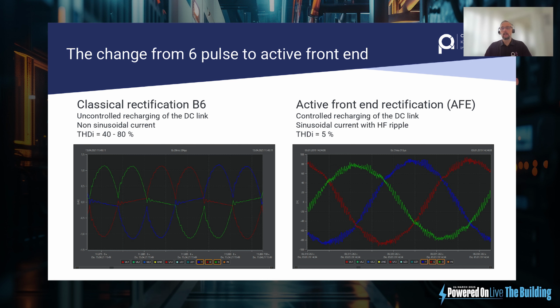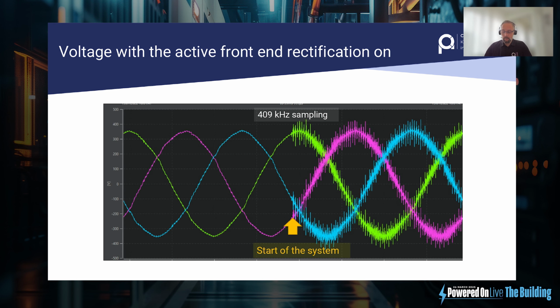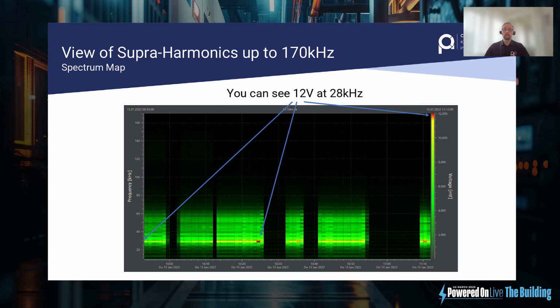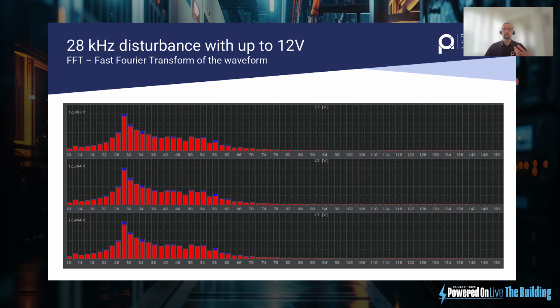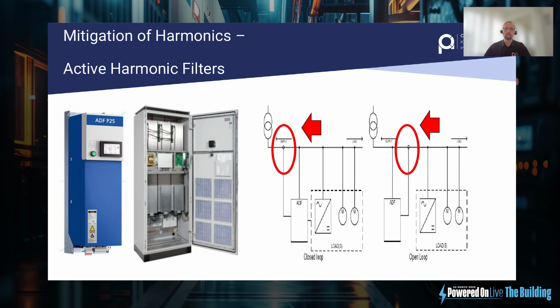The problem is they are low harmonic. You can see there the THDI reading is 5%, but they're overlaid with a super harmonic. You can see a ripple over the frequency. That you need specialist equipment to measure, but that is what causes a lot of problems in sites. And the main reason for that is you need sampling rates of the devices you're measuring to be more than twice the speed of the switching of the device that's making the noise. And from that, we can determine what the noise is, and we can break down where the problem is, and then we can prove by using mitigation what results would be.